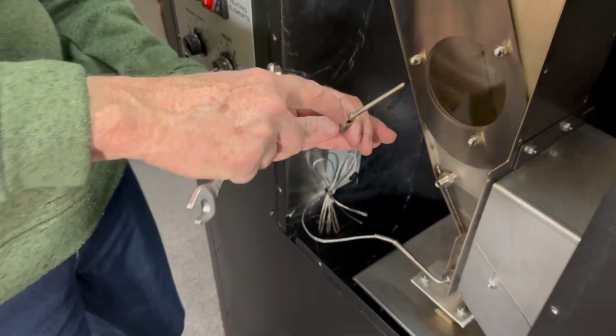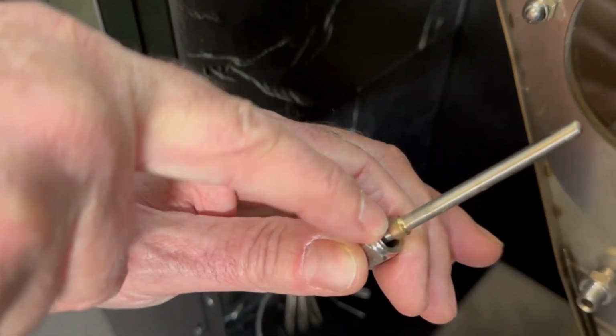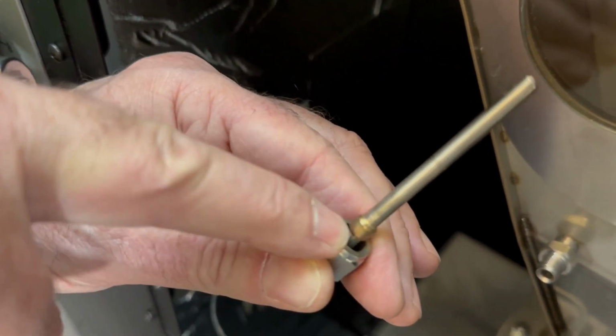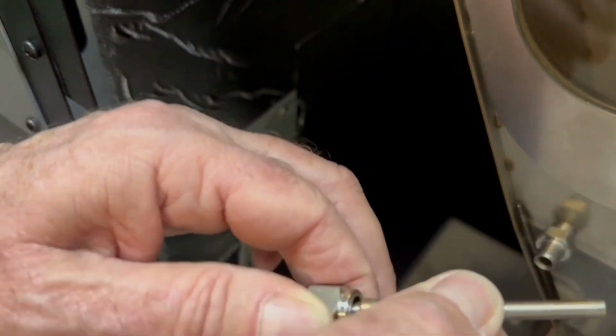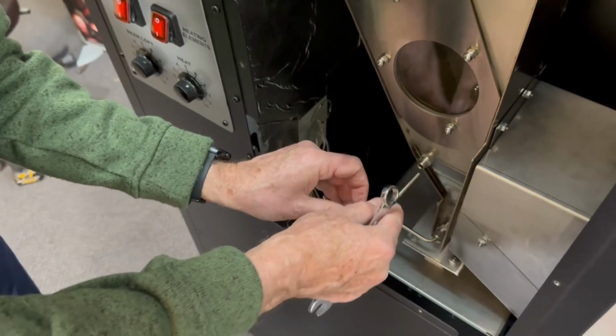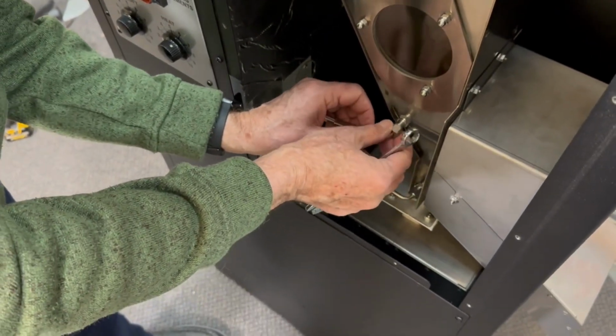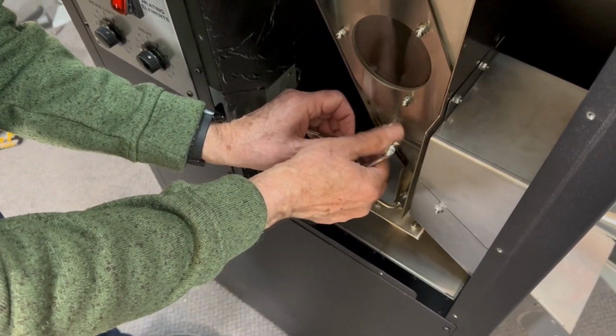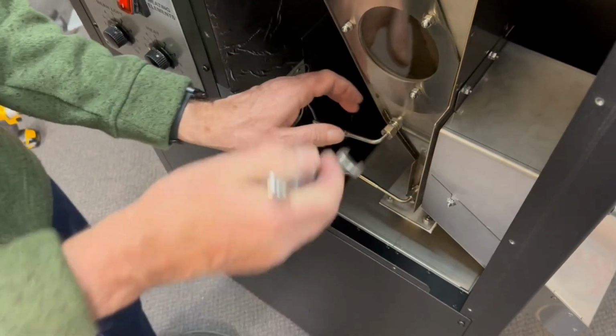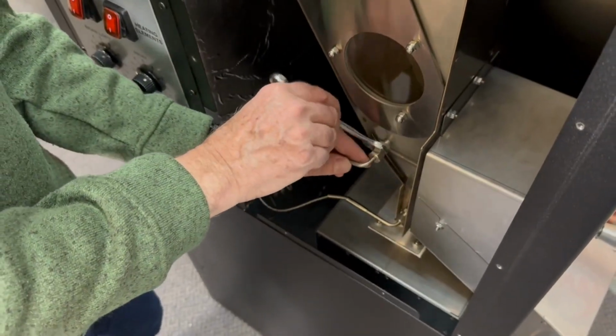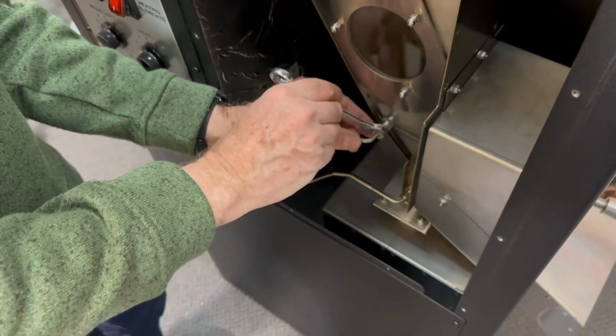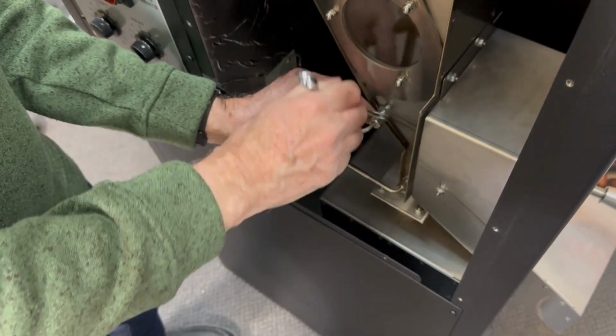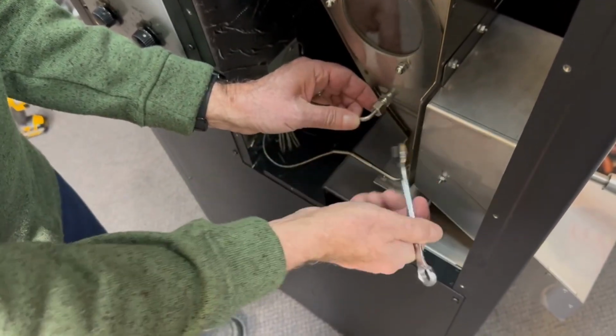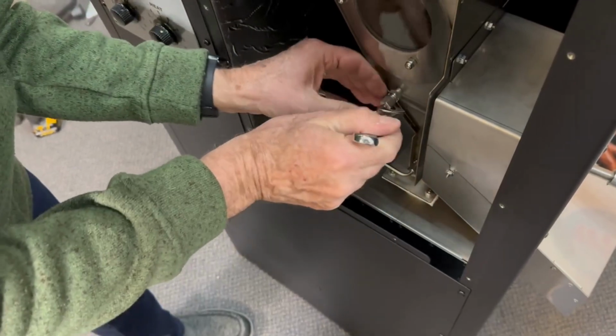Get in here close, Bryce. You'll see that there's a brass compression fitting on there. We have to make sure that that is on there. But then we can just put the other one right back in the same spot. So this is the bean temperature probe. When we put that in there, we make sure that we push it in as far as it can go and tighten it back up.